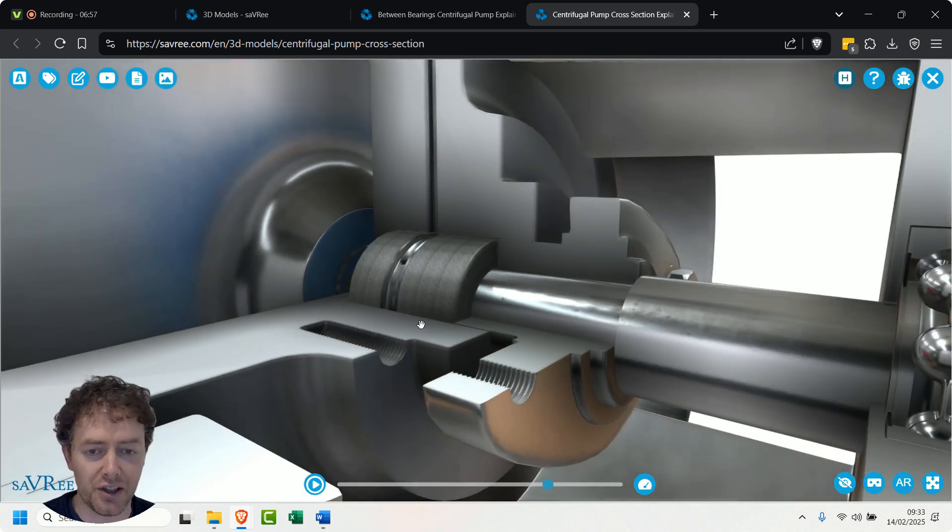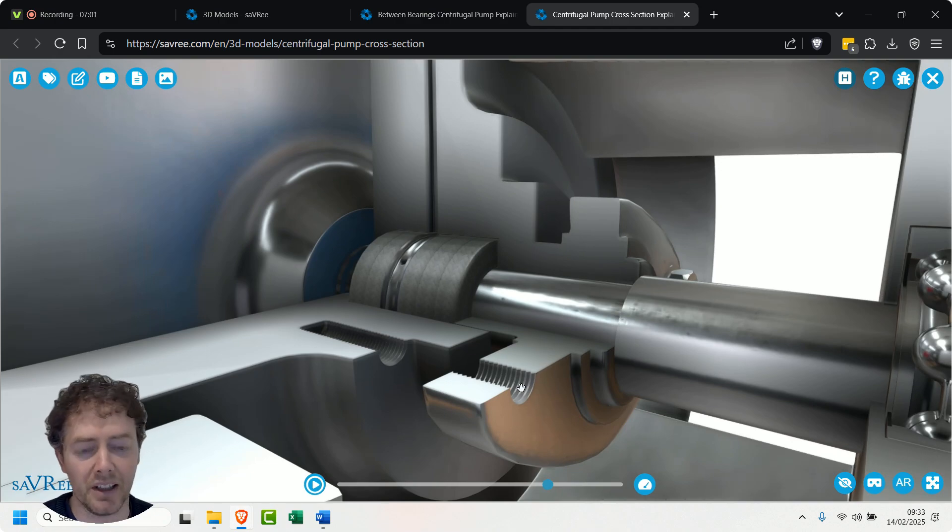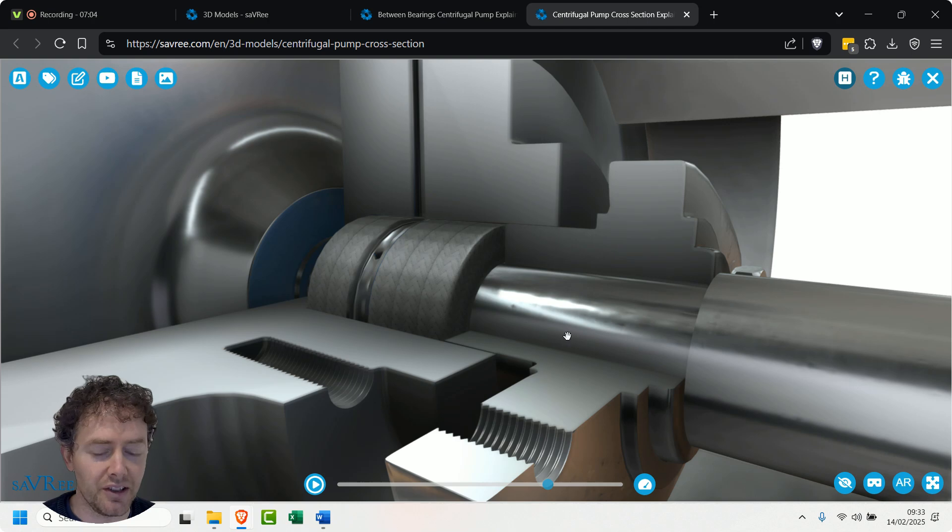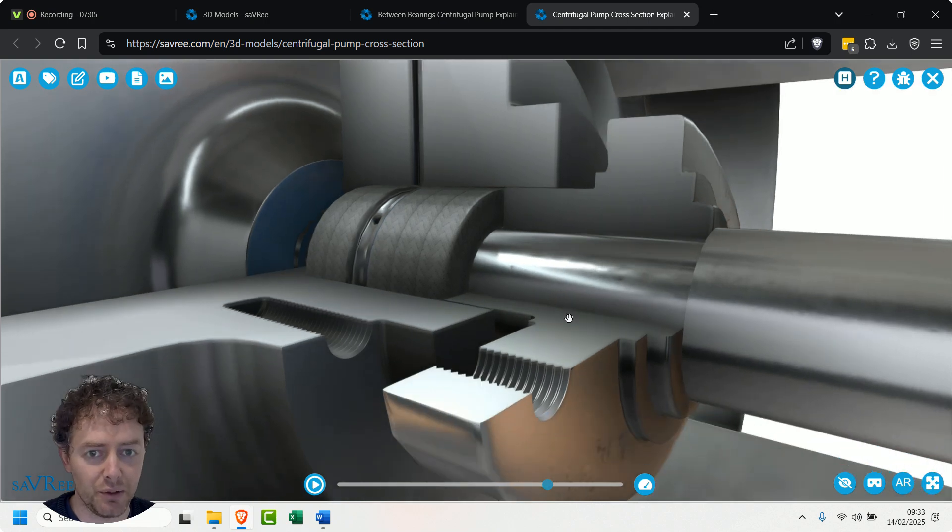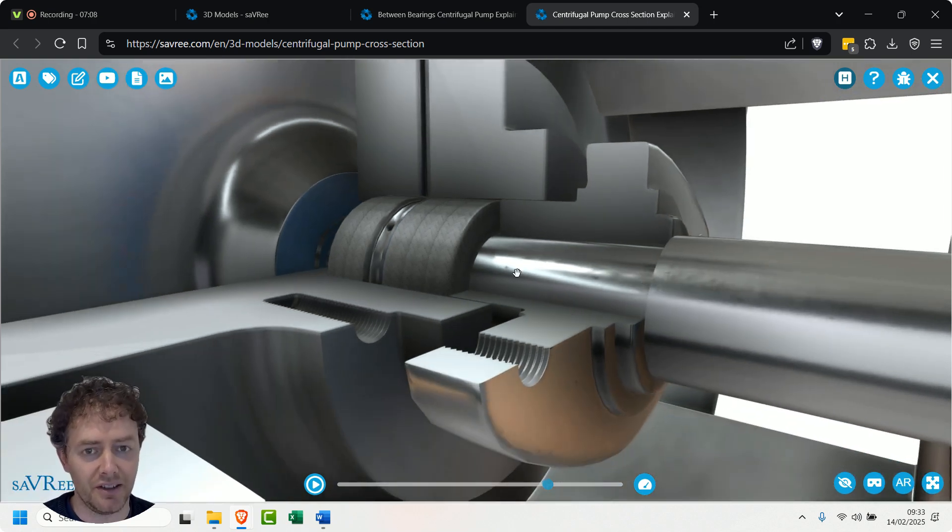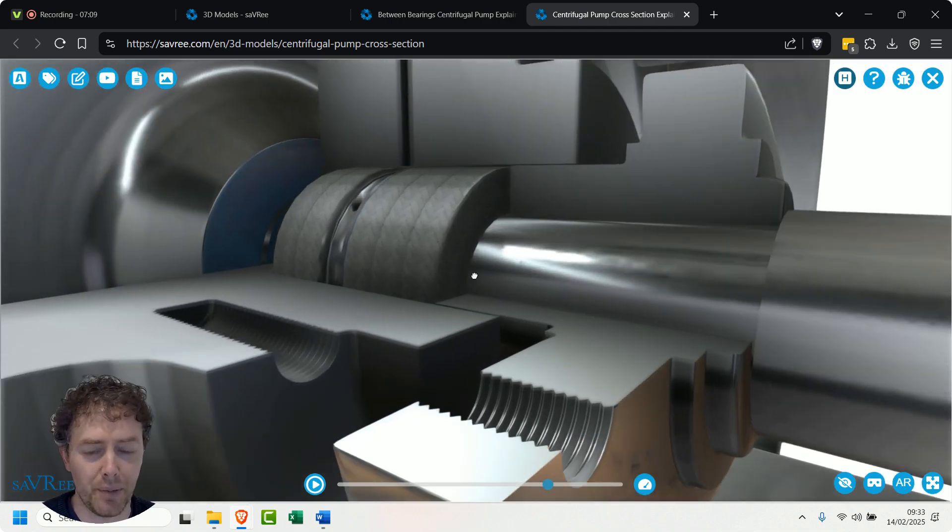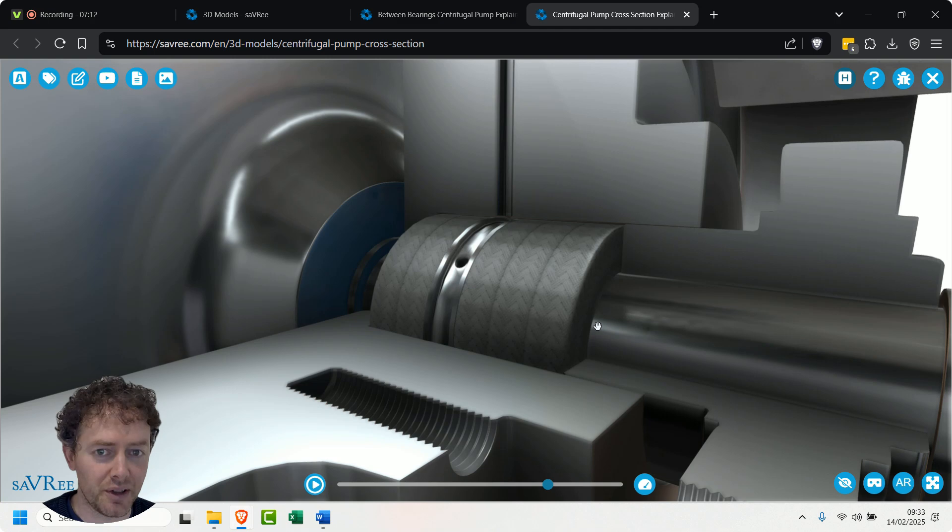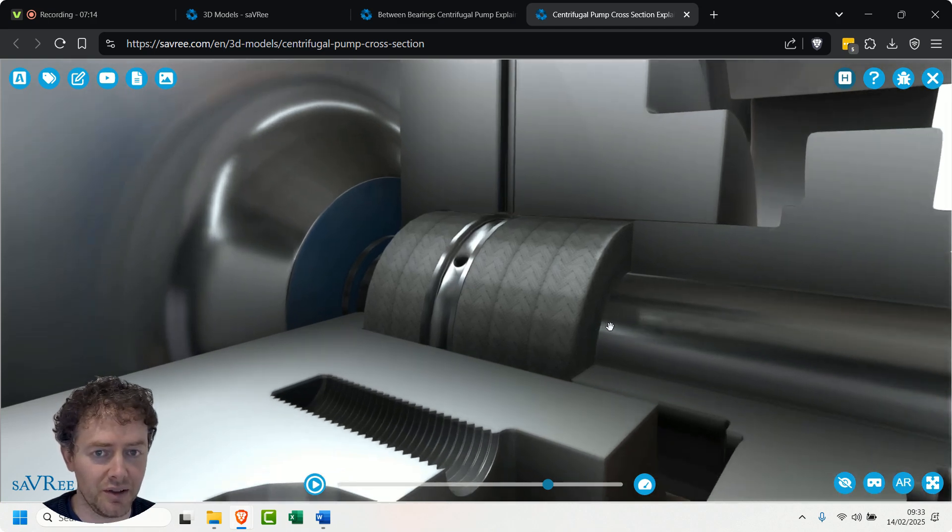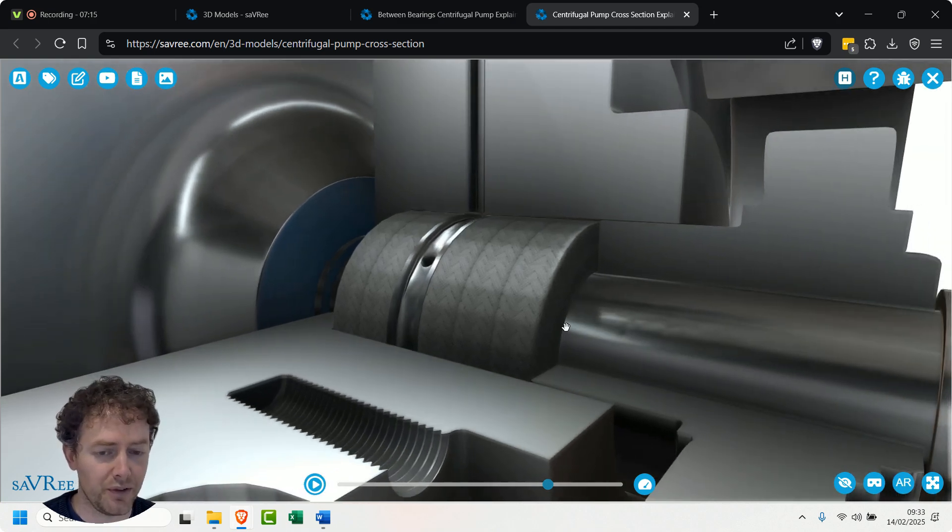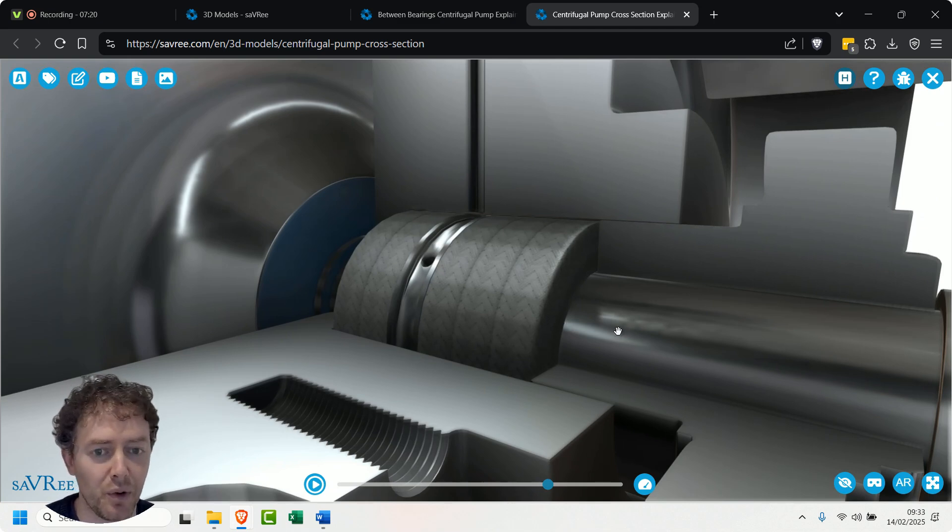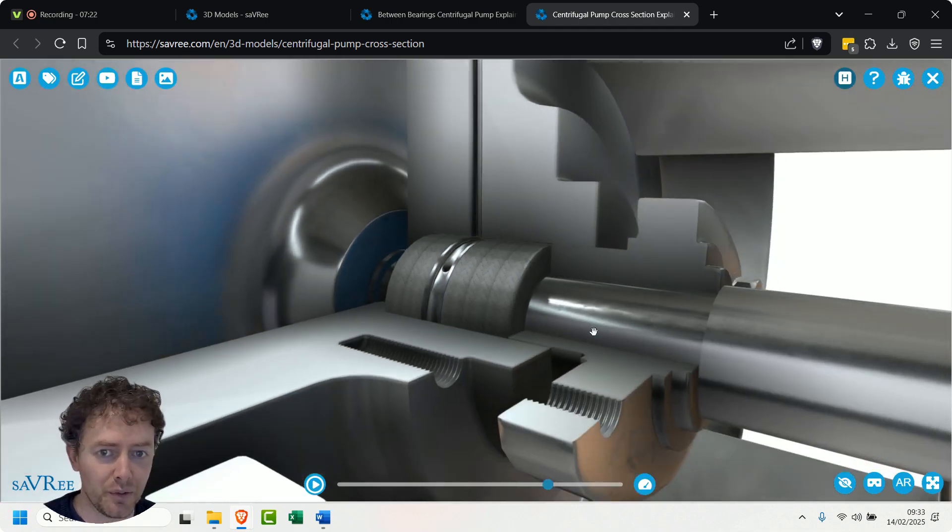You measure the leakage and drippage past the shaft in drops per minute, but that will continually increase. So ideally what you want to do is tighten it up enough that you get the leakage that you require so that the packing is cooled, but not so much that you totally stop that drip rate coming through the pump. And also, you know, you want to stop that excessive wear on the shaft as well.